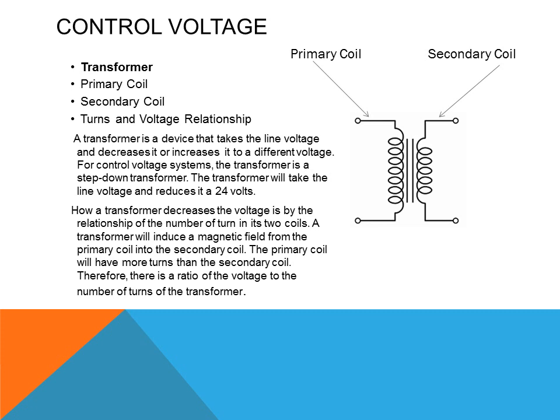A transformer is a device that takes line voltage and decreases or increases it to a different voltage. For control voltage systems, the transformer is a step-down transformer, reducing line voltage to 24 volts. A transformer decreases voltage by the relationship of the number of turns in its two coils. It induces a magnetic field from the primary coil into the secondary coil, with the primary coil having more turns than the secondary coil, creating a voltage-to-turns ratio.